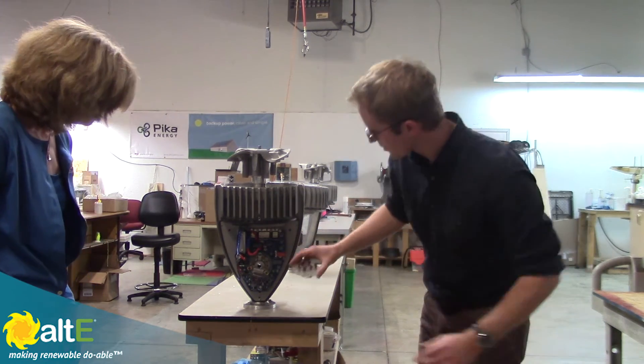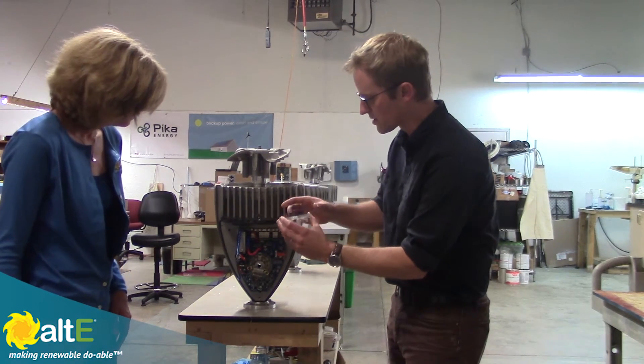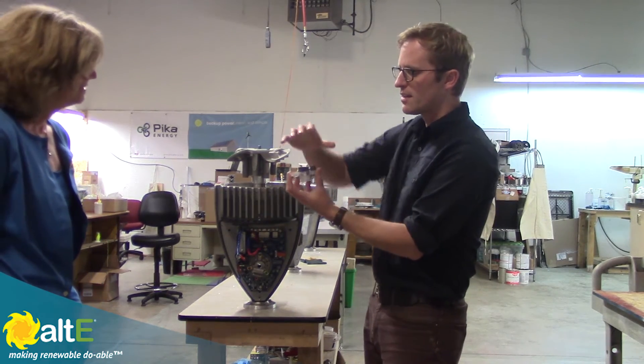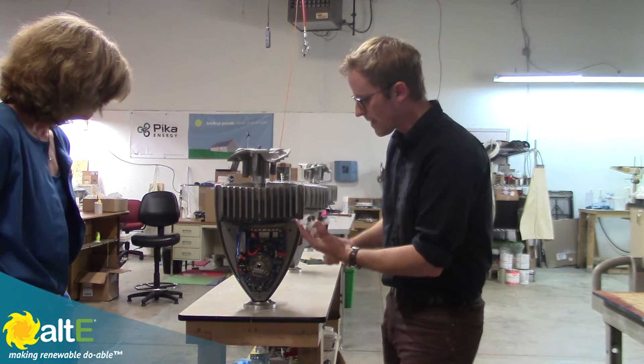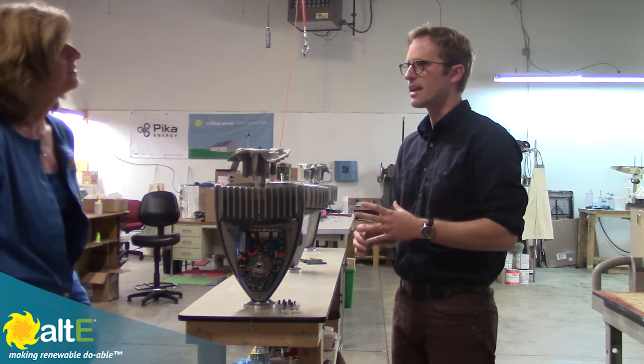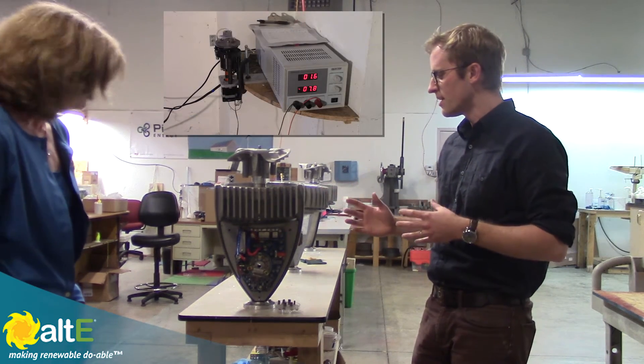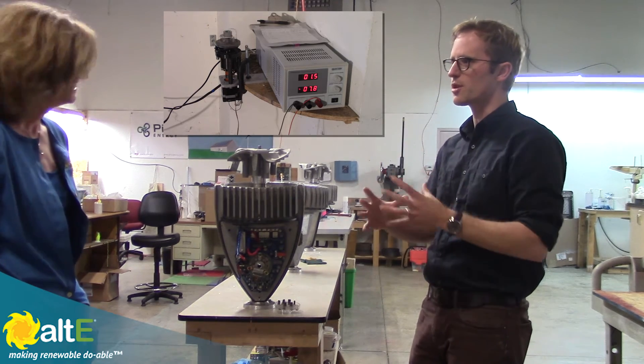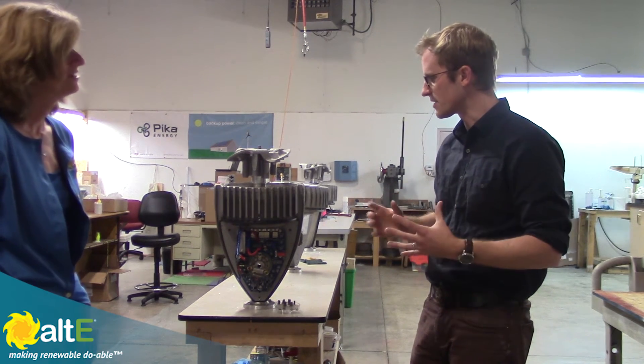And then this right here — here's a close-up of one — is our slip ring assembly for a brush puck. So this is when the turbine is moving around, yawing in the wind. This stays stationary and the turbine kind of moves around it, so the wires don't get tangled. What we do with these brush pucks that's unique is we add double redundant alloy brushes so that they can't fail as easily. We have some simulations set up here where we've been simulating high wind conditions for several years, proving that our brush puck assembly is really resilient and strong — which is a point of failure on some other turbines, so we really sought in our design to overcome that.